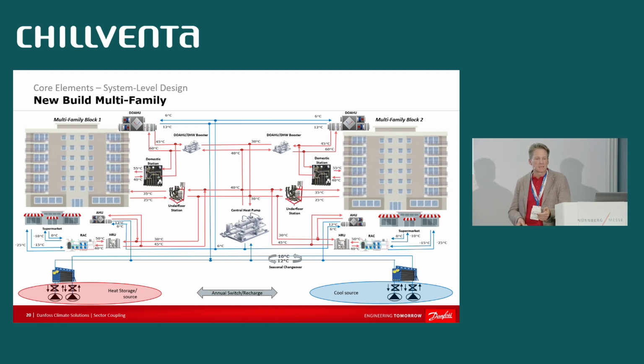Ultimately, to get to the optimal efficiency solution, you have to redesign heating systems with more of a bottom-up methodology: take the highest temperature cooling and the lowest temperature heating, match those up where capacities are close, and then go incrementally from there to design systems that limit the work—the electrical energy—needed to electrify those heating systems.